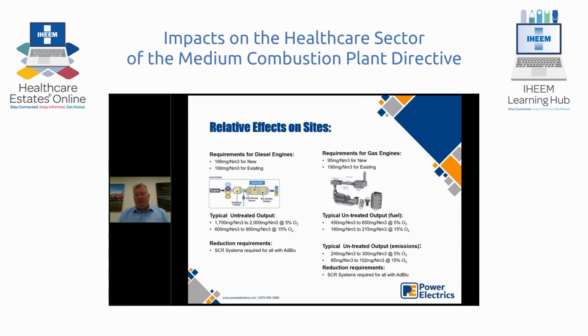So you'll either have fuel optimized engines or emissions optimized engines. The more fuel you burn, the lower the NOx levels. But in some gas systems, you're looking at putting SCR systems in with AdBlue, or just catalyst systems. We have a couple of the range of gas engines we look at which have a level down at 50, but they do have a three-way catalyst in them to achieve this as well.